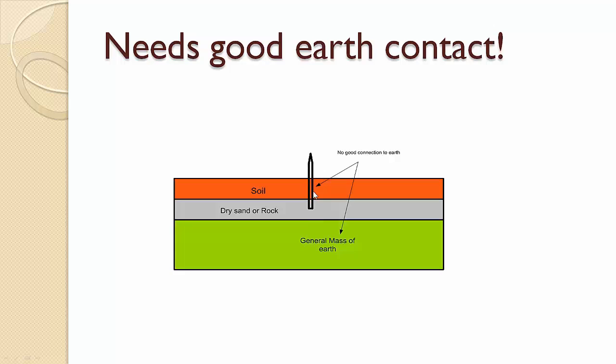which are actually somewhat like an insulator, which prevents the electrode from getting a good contact with the general mass of Earth. So in this case, this is not a good ground. So it will not conduct much current to the Earth.